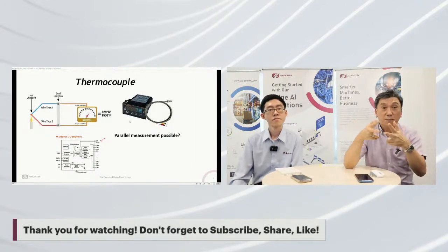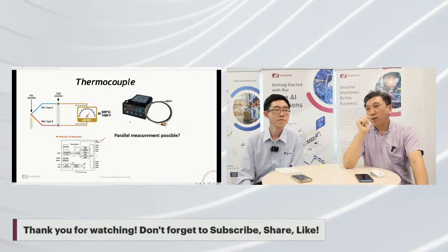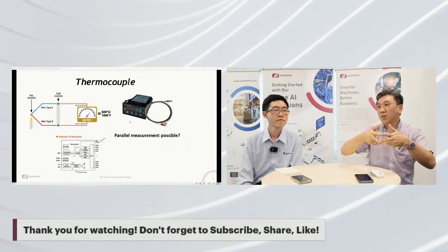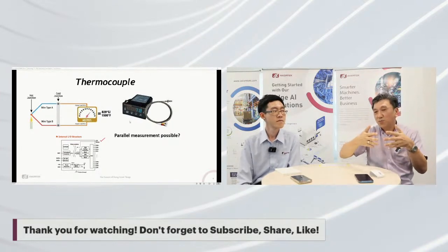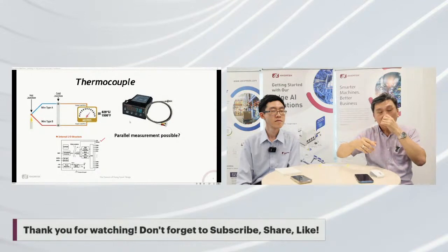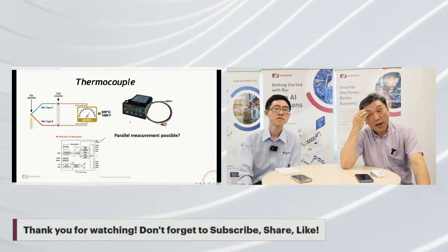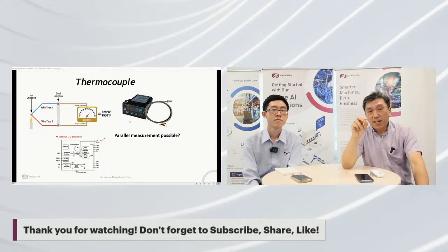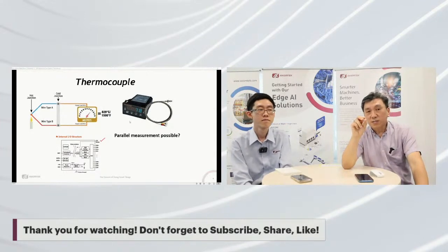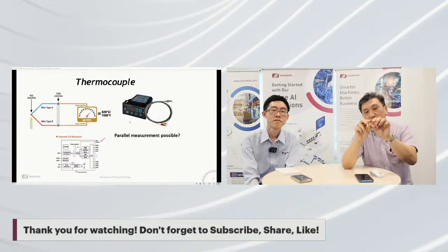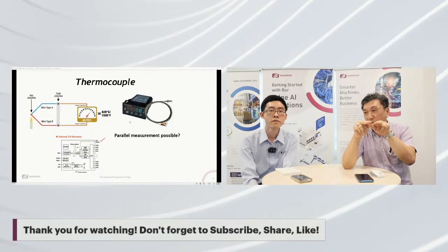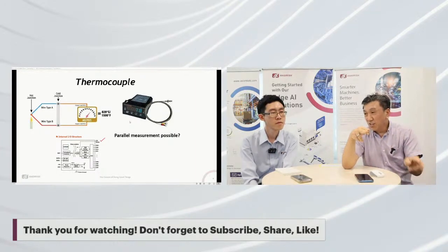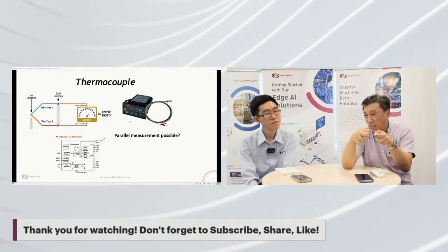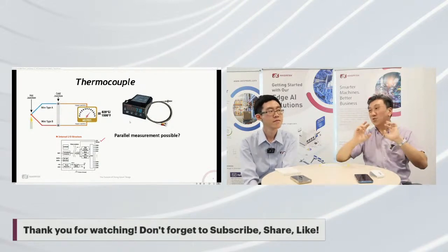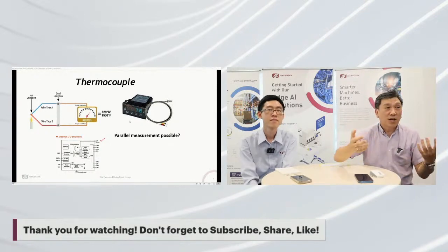That is paralleling. What happens if someone has already paralleled to it? You cannot keep putting too much of this parallel together. So you have another scenario where you need to create another so-called temperature measurement point: you take out the thing and put in a second element of the thermocouple at the same sensing point. That's another way, but it's more expensive, of course.